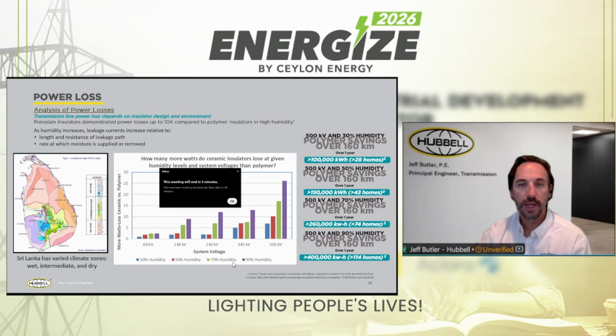And this was taken with the assumption of an average home could be using 3,500 kilowatt hours per year of energy. And so based on that, if we were to use a 500 kV line at 30% humidity, you would be losing over 28 homes worth of power, over 100,000 kilowatt hours. If it's 50% humidity, that's over 43 homes, 150,000 kilowatt hours.